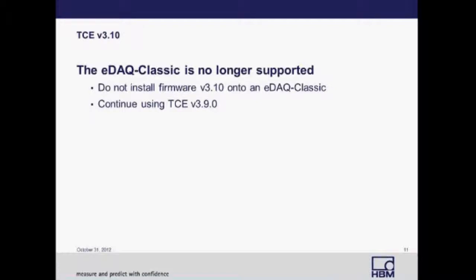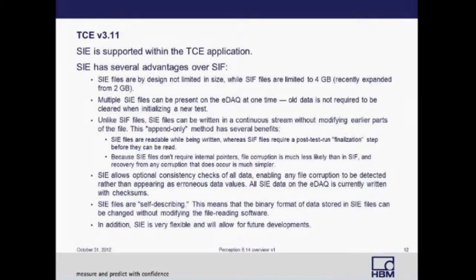In TCE version 3.11, SIE data format is now supported. Acquiring data in SIE format has many advantages over SIF format. The SIF format is limited to four gigabytes, which may be acceptable for most applications, but for long-term testing this could limit the amount of data collected. The SIE format has no theoretical size limitation. Multiple SIE files can be stored on the eDAQ at one time, meaning you can store all your data until testing is complete. With SIF, previous data must be deleted when initializing a new test. Unlike SIF, SIE files can be written in a continuous stream without modifying earlier parts of the file.